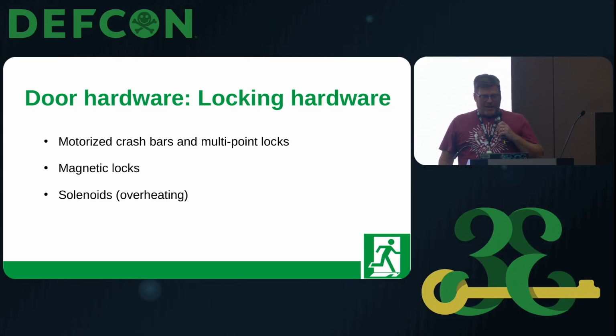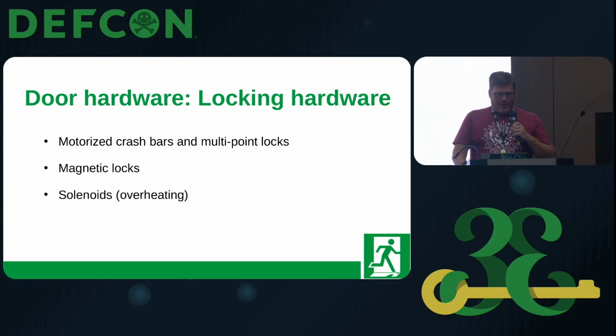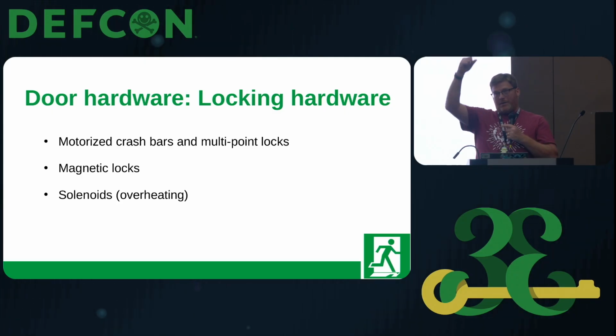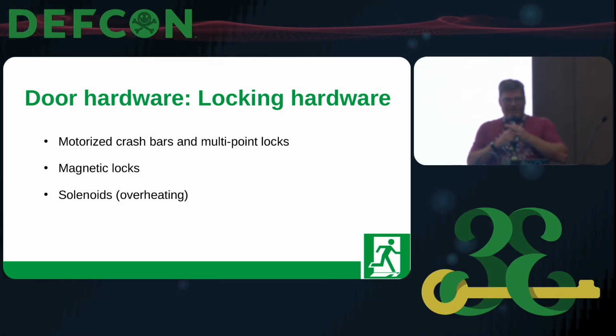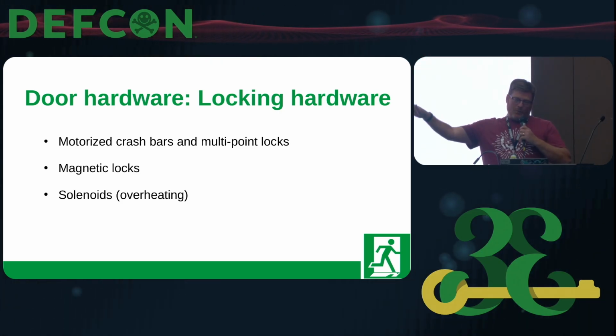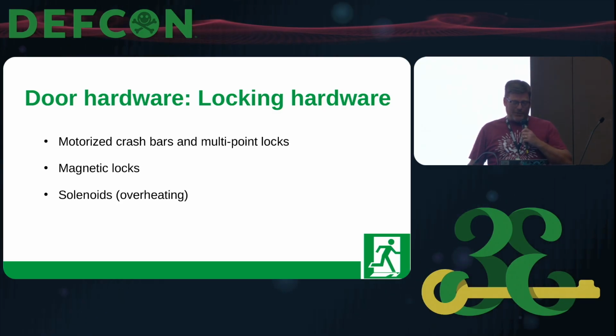I talked a little bit about some of the better locking hardware to deal with motorized crash bars and multi-point locks, where you have a lock on the top and the bottom. And magnetic locks especially take a lot of electricity. So if you're going to do a long run, you have to look at maybe a remote power supply. Maybe I'm going to do 24 volts instead of 12 volts, because I can use the same wire and run essentially twice the power to it.